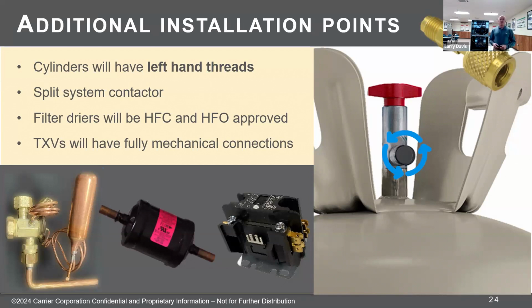Filter dryers, they'll be approved, or they'll say 410A approved or HFO approved. And the TXVs, just like any other system, the TXV has to match the refrigerant that's in the system. That's the way the power head is charged. So the new TXVs for the 454B have to be 454B expansion valves. They'll have mechanical fittings on them.